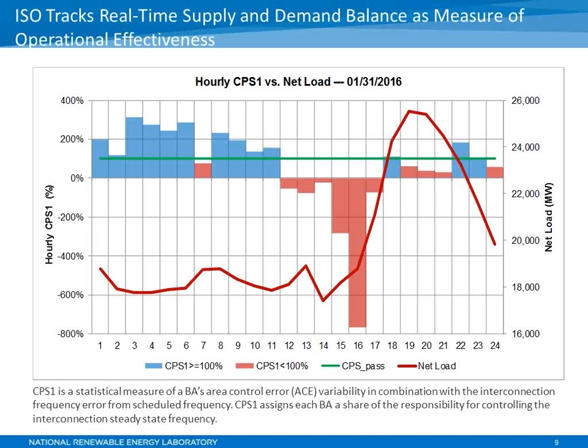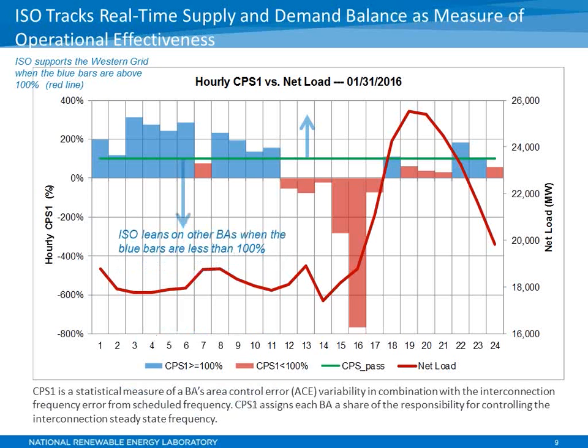If you look at the blue bars, that's when it's above the green line, and that green line is 100%. So everything that shows up blue within the hour means you helped support the interconnection frequency. When you look at the red, you tend to see we had some challenges during those hours. This plot shows you the control performance for that hour, and it also shows you the net load, which is that red curve.